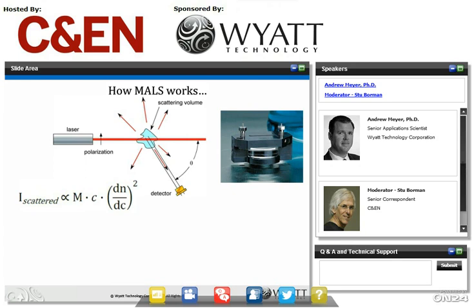That leaves us with this big M. It doesn't stand for magic, but it really is the magic of the light scattering approach. Since we can measure I and C directly with the inline instrumentation, and we can look up the dn/dc value or otherwise know or measure it ahead of time, the molar mass is solved for directly. Of course, this is a very simplified expression of the light scattering equation, but it is at the heart of how this technology works.